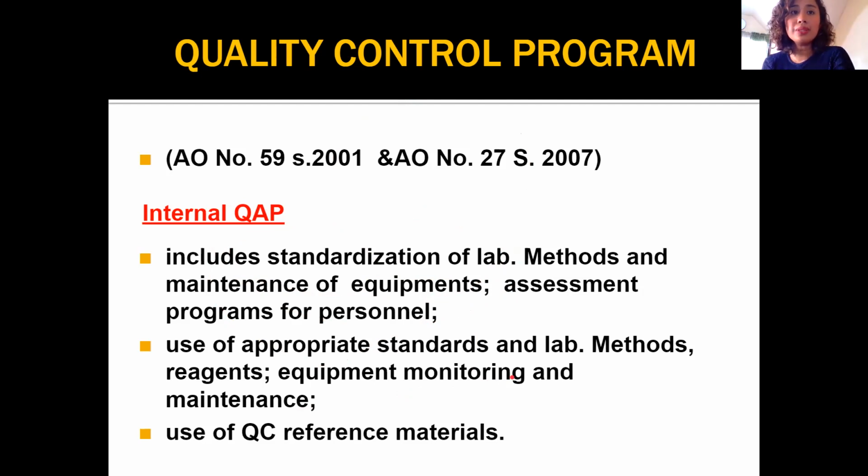Yan. So, to do this, you need reference materials or quality control materials, yung mga reagents na binibili. So, yung normal quality control material, abnormal quality control, abnormally high, abnormally low. Yan. So, pag tinakbo mo yung normal na quality control material, dapat ang labas sa makina mo, normal rin yung result kasi it has a known result.